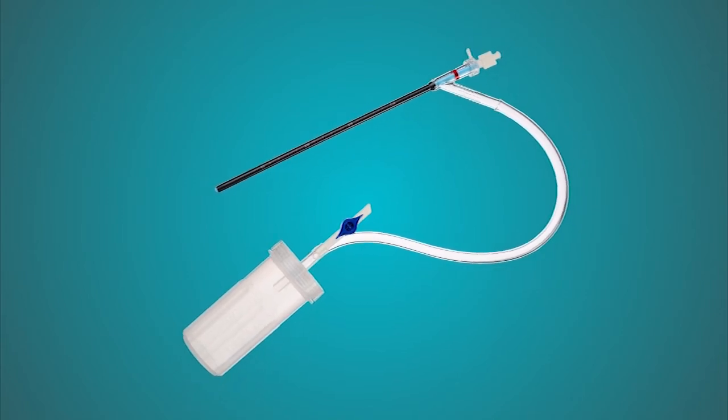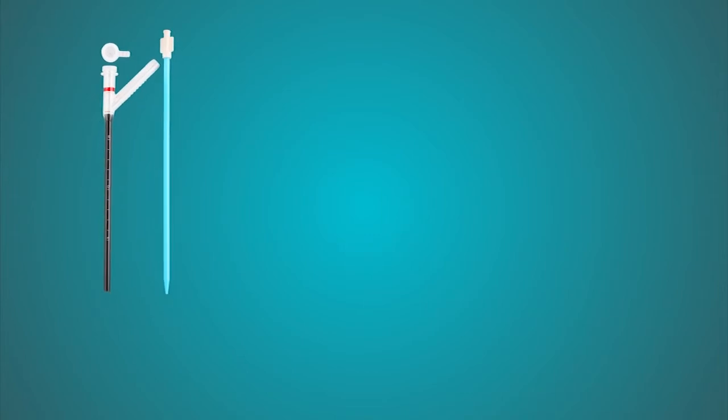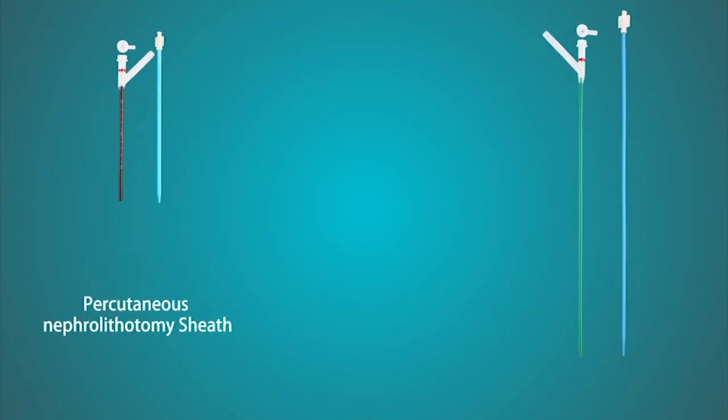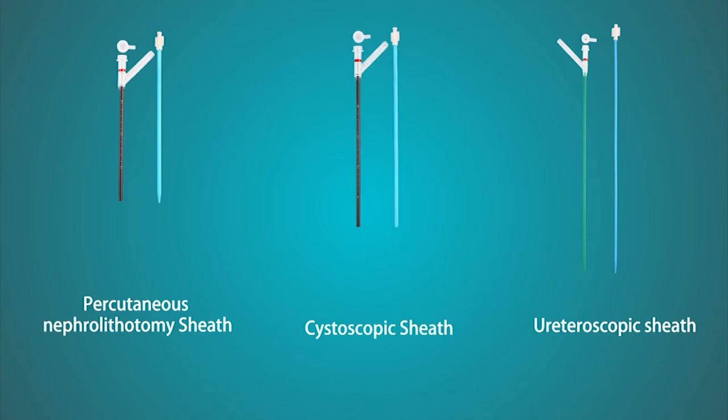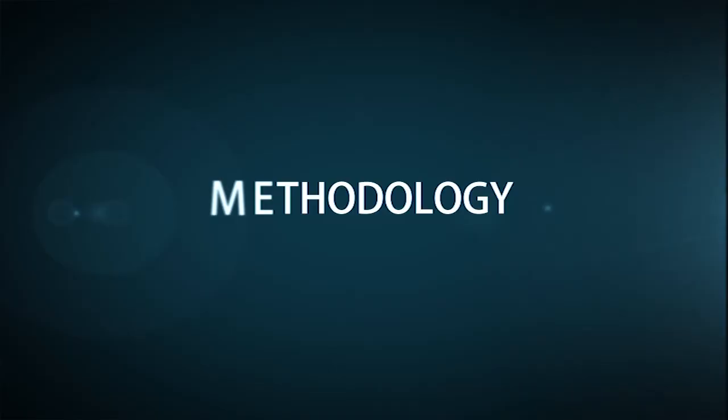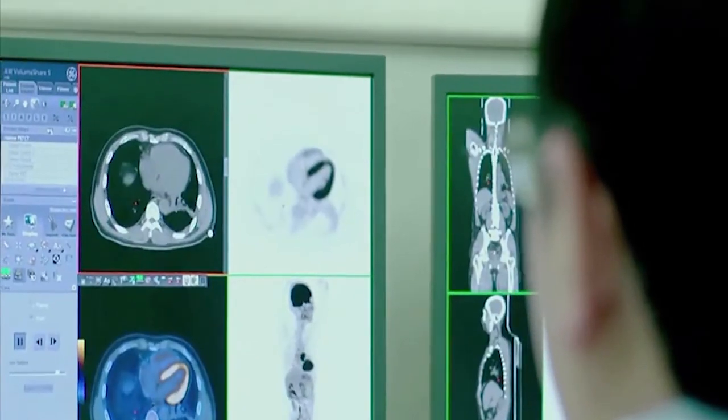Connect the oblique branch of the access sheath to the stone collection bottle using clear and flexible tubing. Our product line includes the percutaneous access sheath, the ureteral access sheaths for the kidney and ureter, and the cystoscopic access sheath. After routine preoperative preparation, select the appropriate sheath according to the stone location and surgical technique.